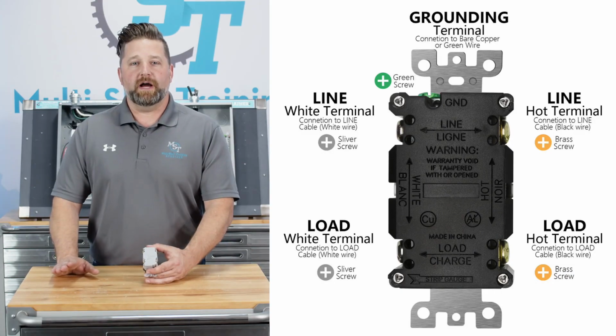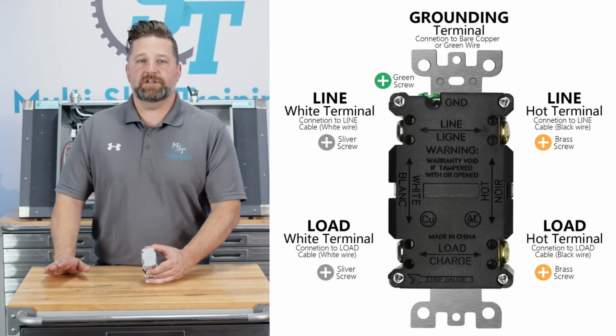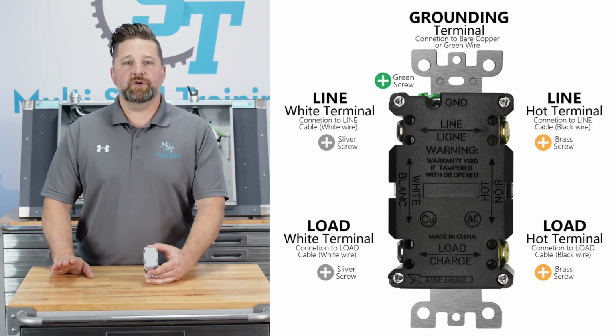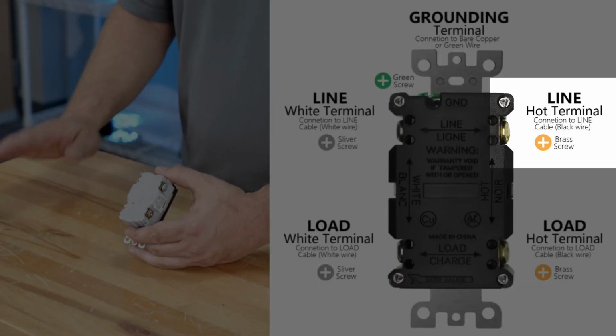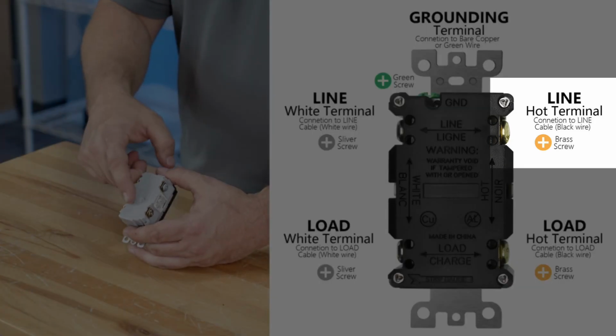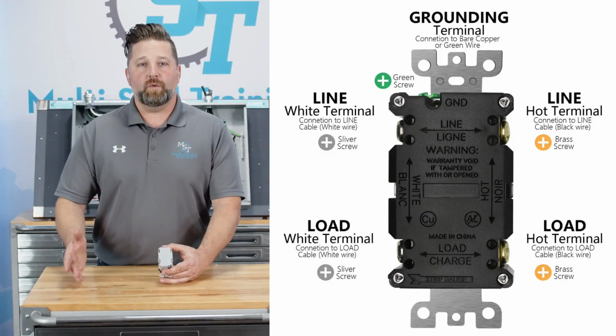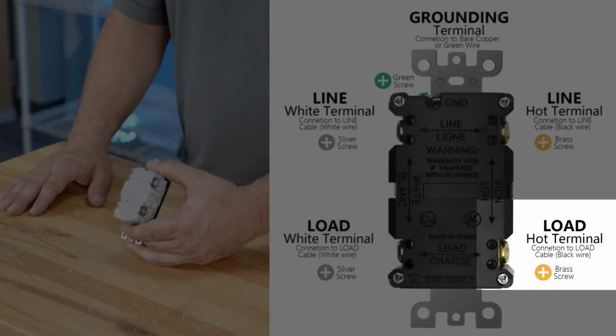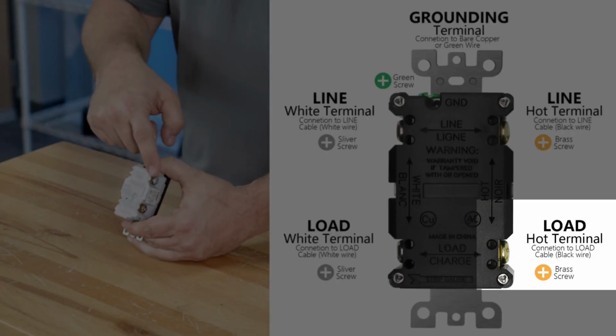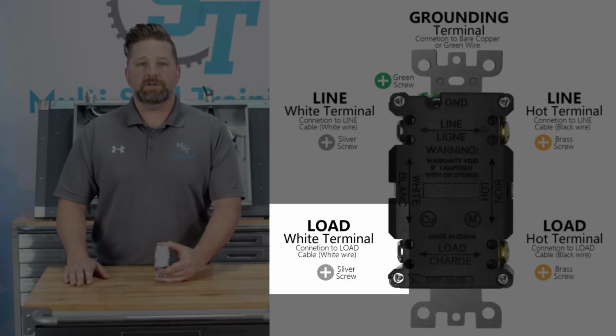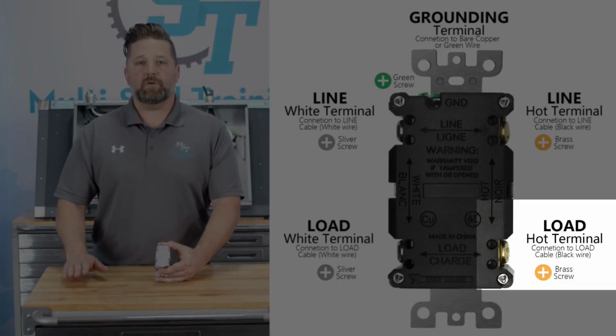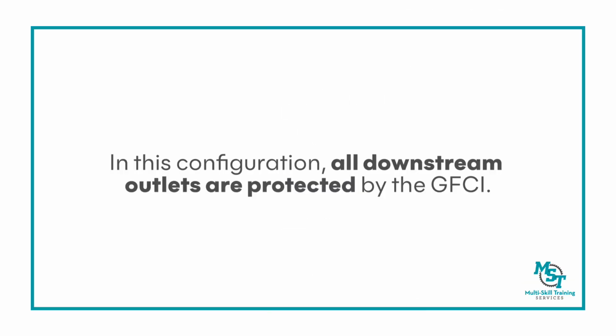The second wiring option allows the GFCI to protect additional outlets further downstream on the same circuit. Incoming power wires from the panel connect to the line terminals, while the other wires supplying downstream outlets connect to the screws labeled load on the top. The white wire goes to the silver load screw, the black wire to the brass load screw. In this configuration, all downstream outlets are protected by the GFCI.